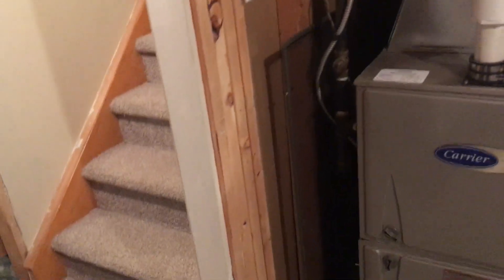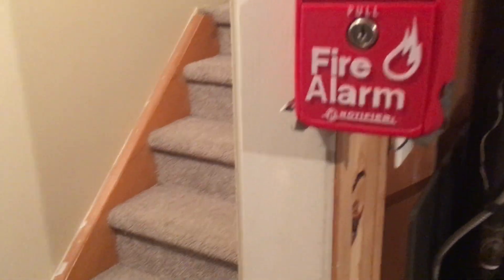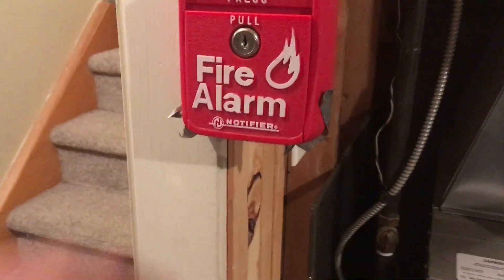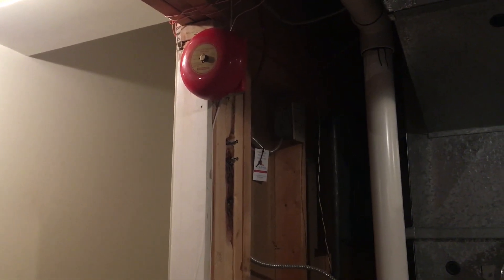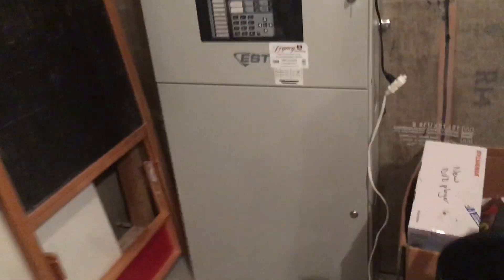I have it set up to just silence itself after the four rounds rather than switching the bells to continuous. Each pull station does its own separate code, and that code will do four rounds and then silence itself. So without further ado, here we go — I think this pull station is 2-4-2, so here we go.